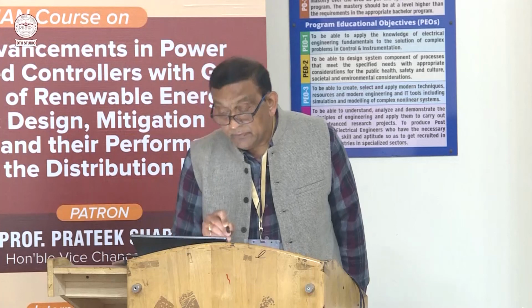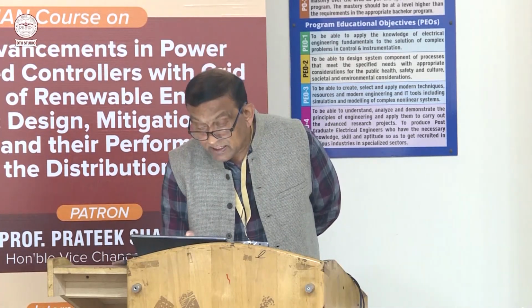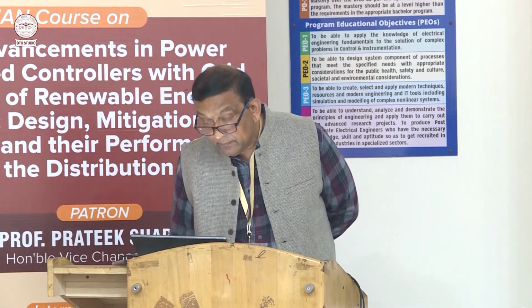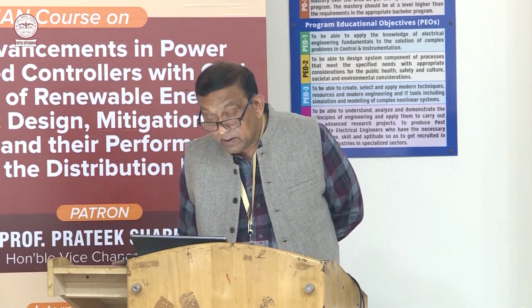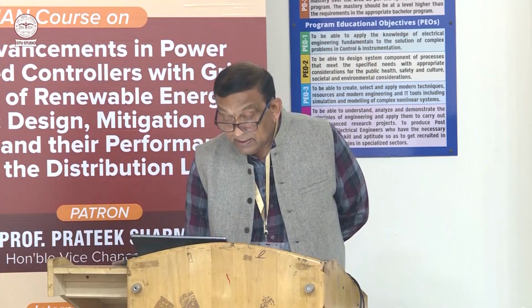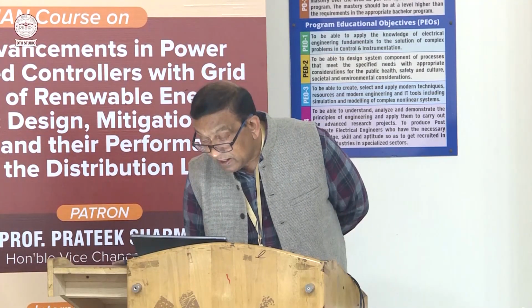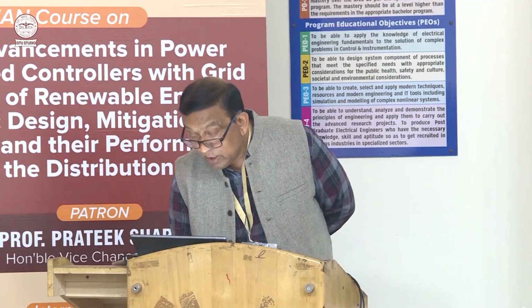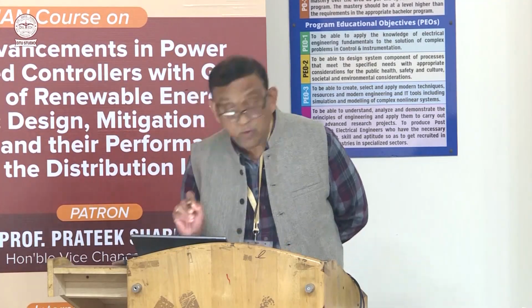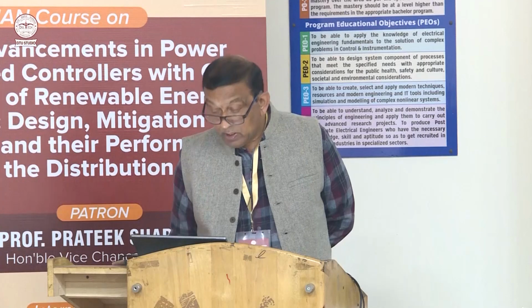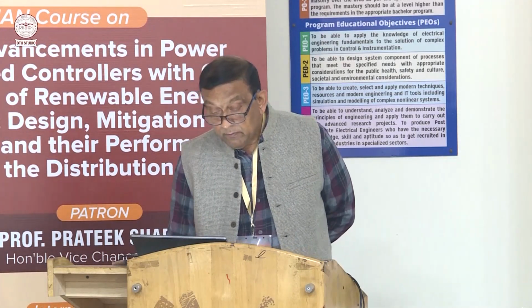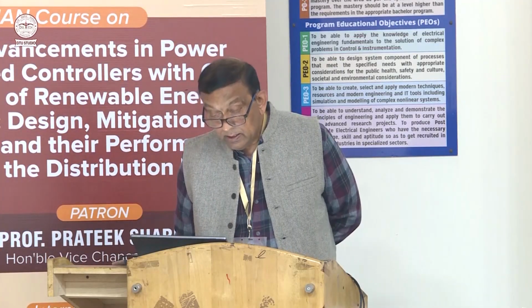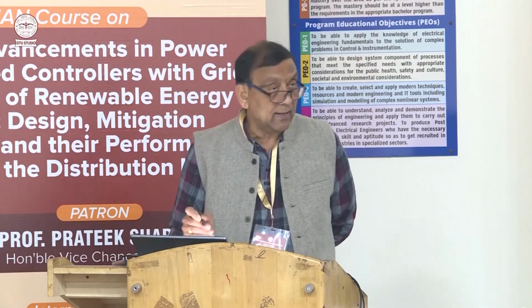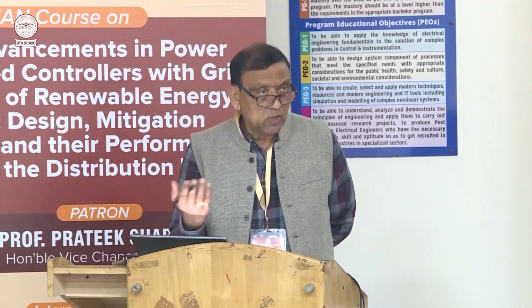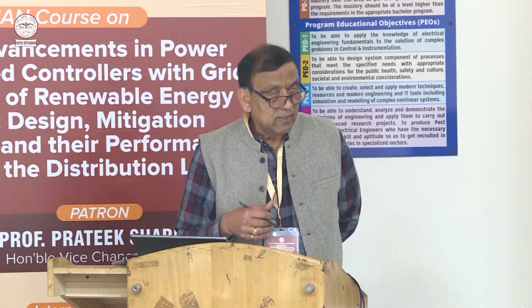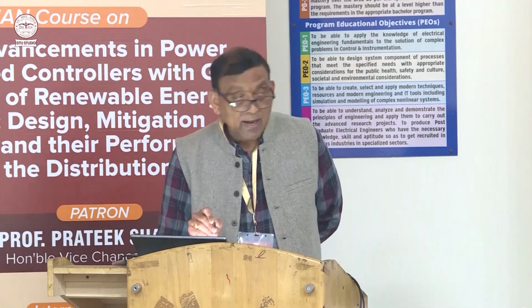But talking about TDD, this is for large industrial plants, and you can see this is the same as we have in THD, starting from the second harmonic. But here you see this is the RMS value of the maximum fundamental load current, IL, calculated as the average of the maximum monthly demand currents for 12 months. So instead of putting I1 here, which is the RMS current of the fundamental component, here it is more complicated to calculate IL, and in some cases data may also not be available, so it's not that easy to calculate TDD.